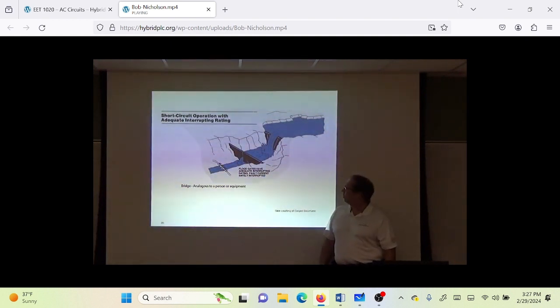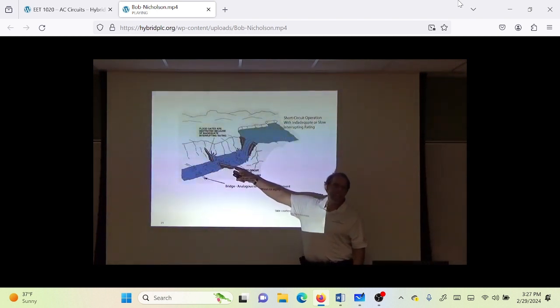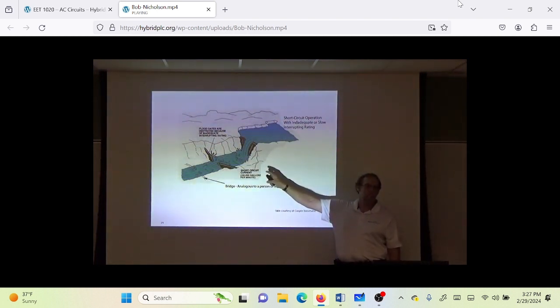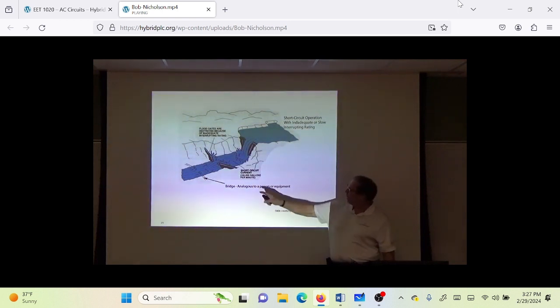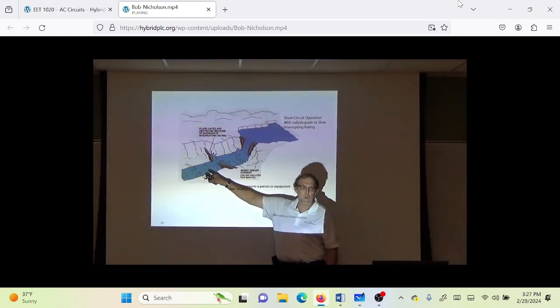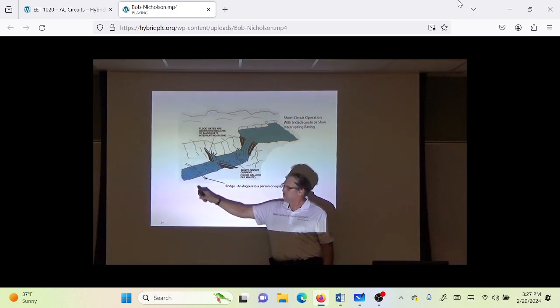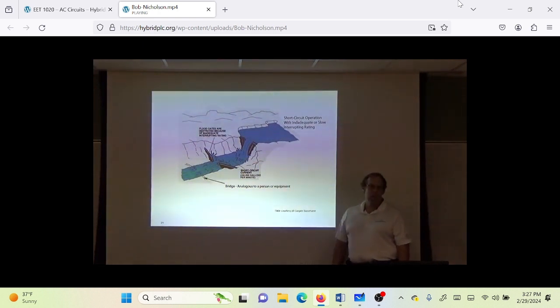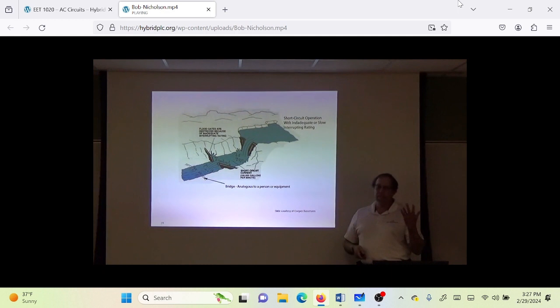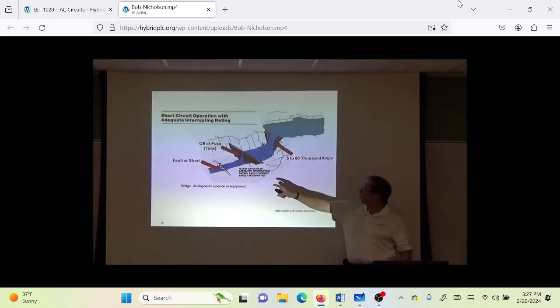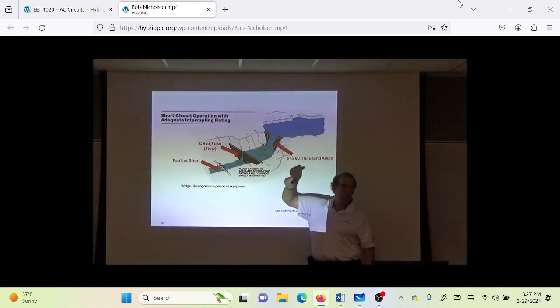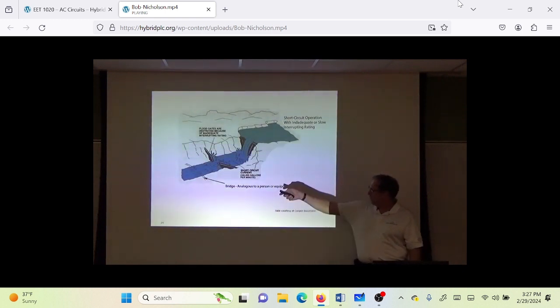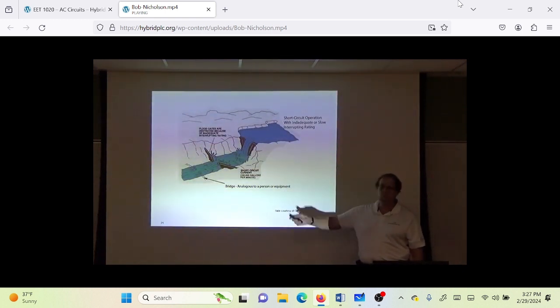The problem is, if this takes 1/10 of 1 second to open the circuit, it's going to allow 30,000 amps past it, right to there. Now the arc flash is going to occur. You're in it. I don't think 1/10 of a second is a long time, but it is an eternity in an arc flash. The arc flash is going to begin, and then it'll eventually get shut off when that turns it off. But the problem is, it's going to be right there. The transformer is going to get you.